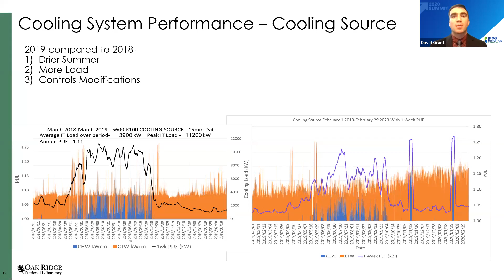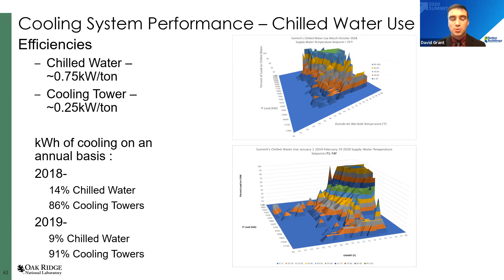So here you can see the biggest savings going from the chill water to the cooling towers in the kilowatt per ton. So this is the kilowatts of electricity used by the facility in our centralized plants. And you can see the difference between the total BTUs that we handled with the two systems between the 2 years. Next slide, please.